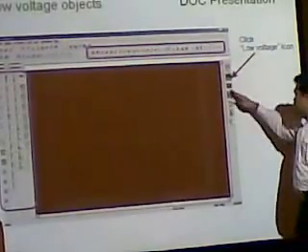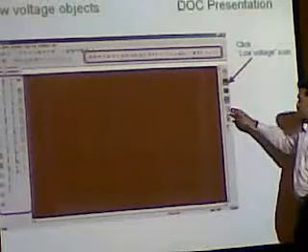Sometimes in a coordination table, you may not be able to get the coordination. But by adjusting the setting ranges, we can draw the curves. We can draw the curves of upstream and downstream, and we can show the customers that they are not clashing together. So for that purpose, we can use the curves. The accelerators we will not use.